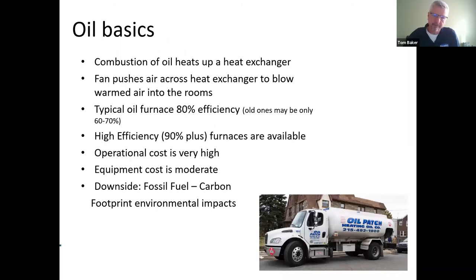If we go to oil as our fuel source, it functions the same way. With our better furnaces today, we can get up to 90% even with oil. The operation cost, therefore, is going to be high. In fact, it was the highest heating cost on that chart we saw earlier. The equipment cost is about the same as gas or propane. Carbon footprint is the same problem. It creates a negative impact on the environment. And those three are all still very common. Oil has become less common than it was 20 years ago. But if you take oil, propane, and LP, or natural gas, it represents a pretty large percentage of the heat sources found in the Northwest.